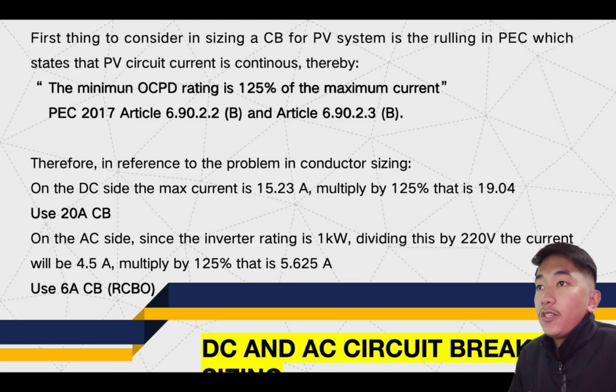Circuit breaker sizing. First thing to consider in sizing a PV system is the ruling in PEC, which states that PV circuit current is continuous. Thereby, the minimum OCPD rating is 125% of the maximum current. PEC 2017 Article 6.90.2.2b and Article 6.90.2.3b. So the PEC categorized the photovoltaic circuit as continuous. And to compute our current, kung ano yung maximum current, dagdagan lang natin ng 25% and yun na yung size ng circuit breaker.